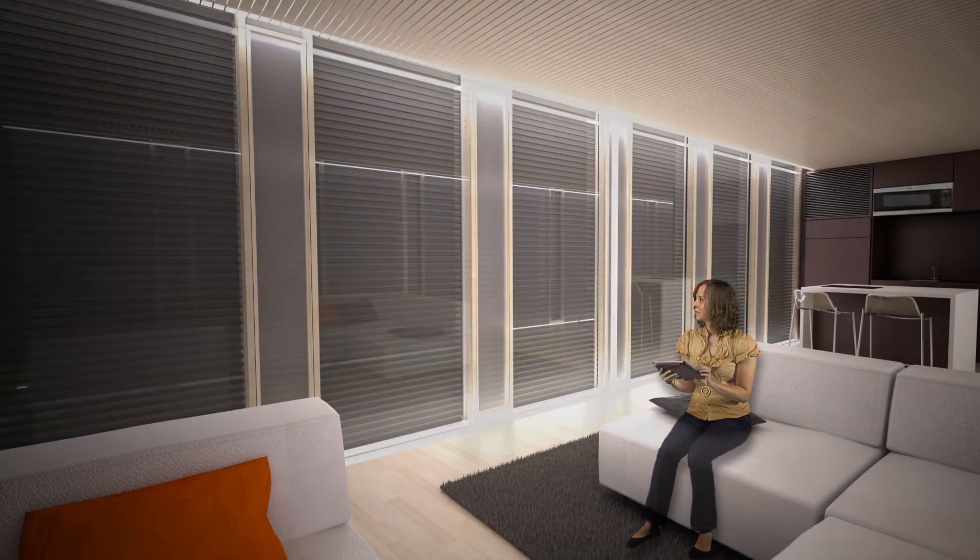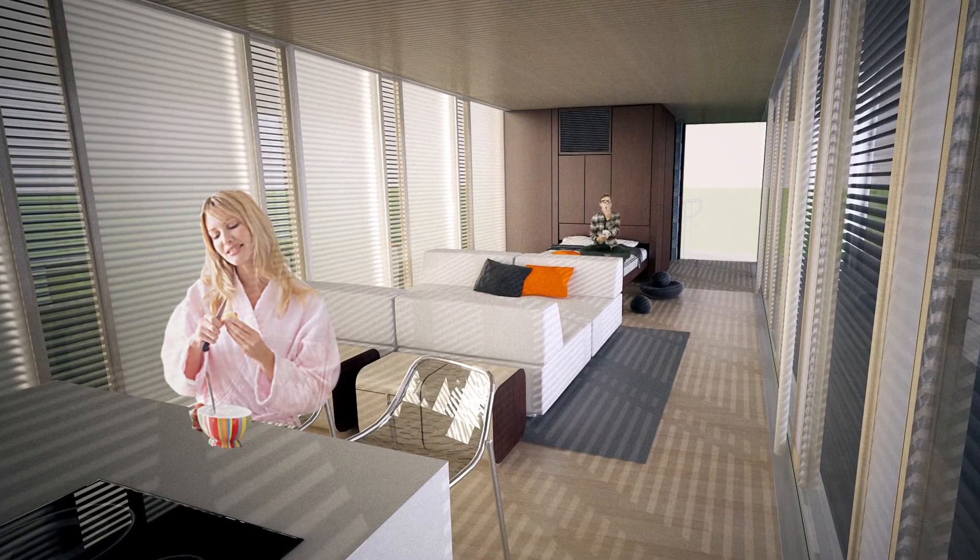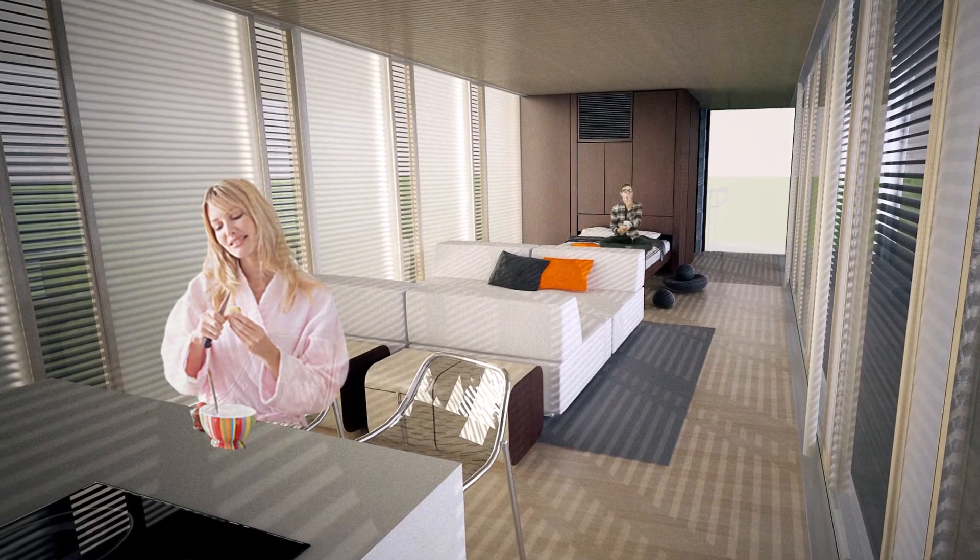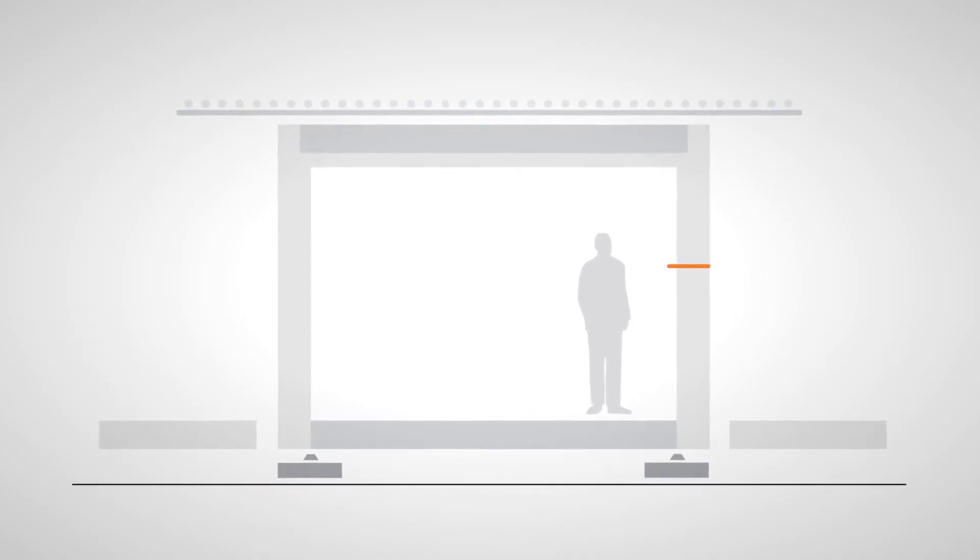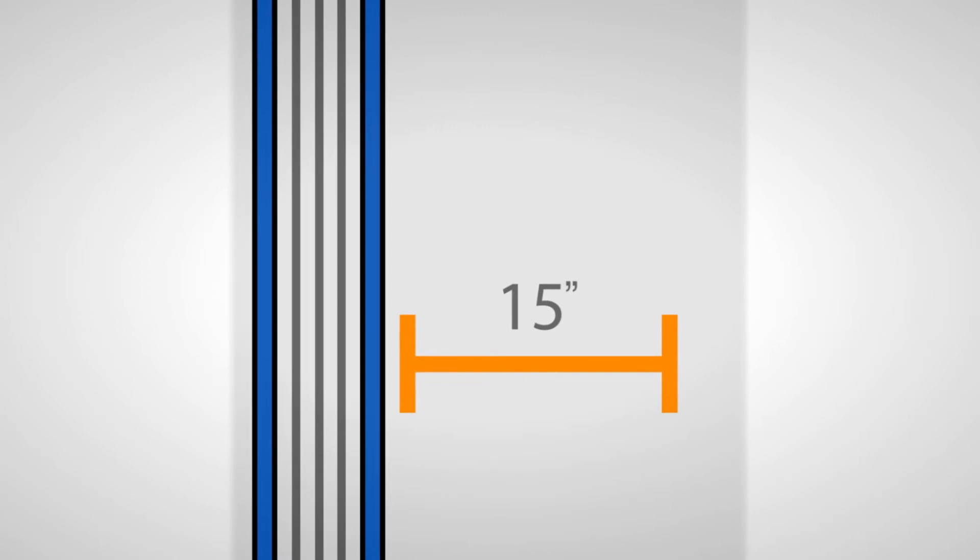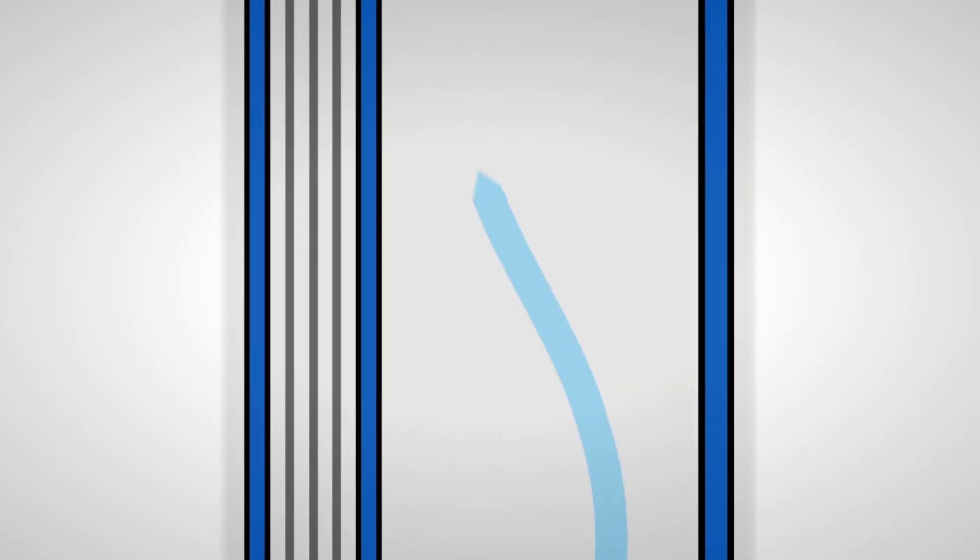The double glass facade solves the design challenge of maximizing transparency, views, and natural lighting without compromising the thermal envelope. It consists of an inner insulating double pane window separated by multiple mylar films. A second glass pane is spaced 15 inches from the interior window, creating a ventilated air cavity.